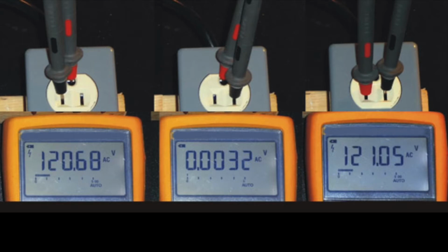So if you put one hand on the hot and one hand on the ground, you're going to get shocked. And if you put one hand on the neutral and one hand on the ground, you're not going to feel anything. And if you put one hand on the neutral and one hand on the hot, you're going to get shocked. Because the ground and the neutral are at the same potential because they're connected, you don't have to worry about a large difference in potential that can create large currents.